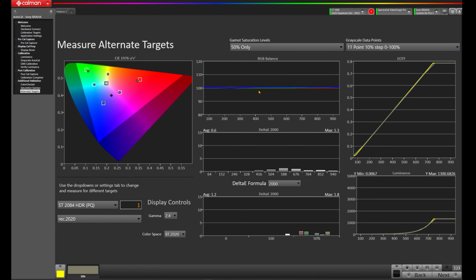The RGB balance looks pretty good here. Our Delta E2000 is a max 1.3 with an average of 0.6, and our colorimetry on the Delta E2000 has a max 1.8 with an average 1.2. And again, we can see we have a little bit of saturation issue here on the red, but we did see that in the SDR where we had a little bit of mismatch with the red, so I'm not too worried about that here. It looks like it's translating over.